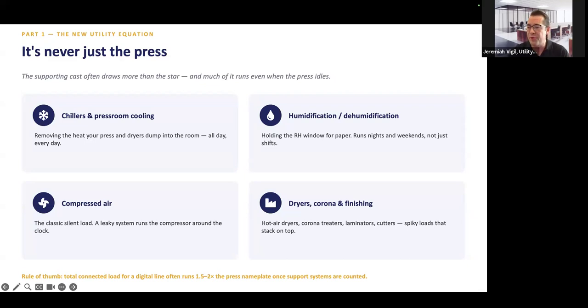So what a lot of people do is think, I'm going to turn off the humidifiers or turn them down on Saturday and Sunday when no one's in the office, then on Monday turn them back on to full capacity just to save a little on the kWh or electricity usage. But when you do that, really all the savings goes away, because on Monday it has to overload and work basically twice as hard, and it could take all day just to get that humidity back to where it needs to be.